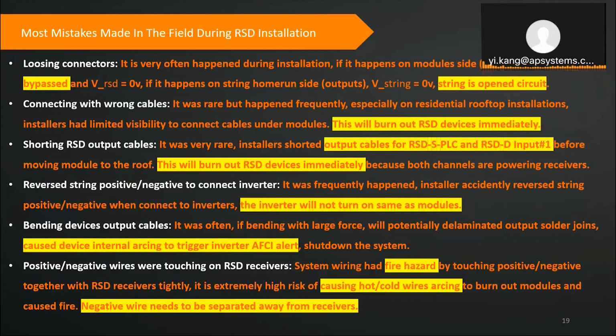What's the failure rate so far in reality? What's the most common mistake made in the field during RSD installations? Losing connectors. That's the most common, very often. Connection with the wrong cable, I have experienced in real installations. For some reason, they just crossed them. What that means is they use one output to install to another site or input somewhere. They mix up the cable, then they burn out the device. Shorting the RSD output cable, yeah, please pay attention. Do not short the output cable. That will directly damage the device.